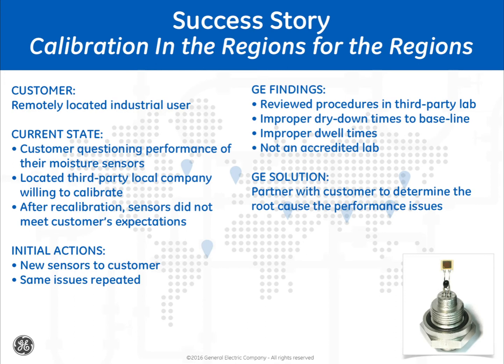We are now working directly with this customer, with their probes, and on their applications to determine why these sensors are not performing to meet their expectations, without the added complexity and uncertainty of a third-party calibration coming between us. Now that the sensors are coming back to us, the physical evidence shows that something in the application is attacking the sensor, changing its calibration. This could not have been resolved as long as the sensors were not coming back to the factory.